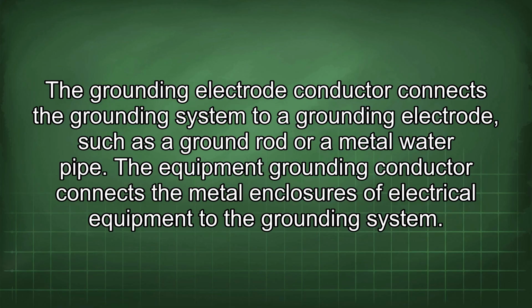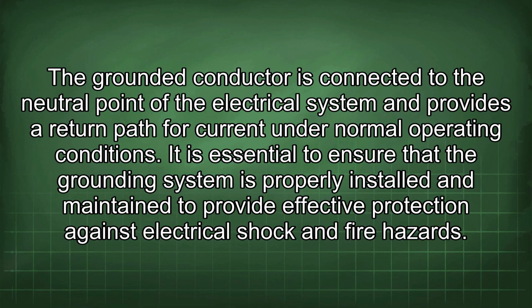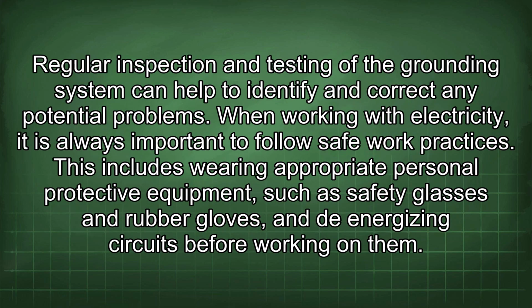The equipment grounding conductor connects the metal enclosures of electrical equipment to the grounding system. The grounded conductor is connected to the neutral point of the electrical system and provides a return path for current under normal operating conditions. It is essential to ensure that the grounding system is properly installed and maintained to provide effective protection against electrical shock and fire hazards. Regular inspection and testing of the grounding system can help to identify and correct any potential problems.